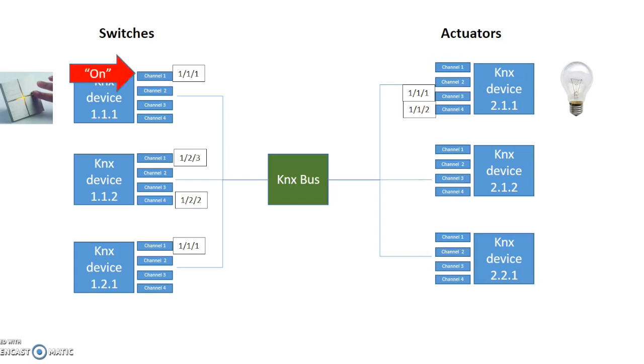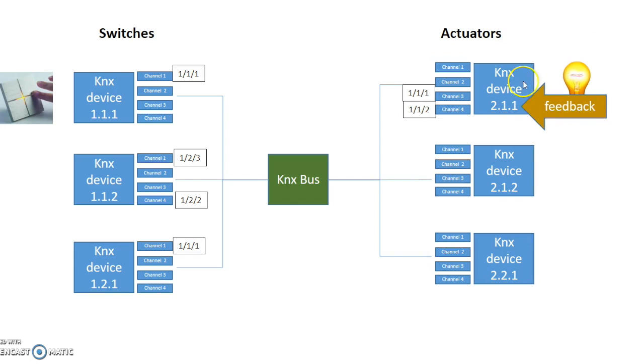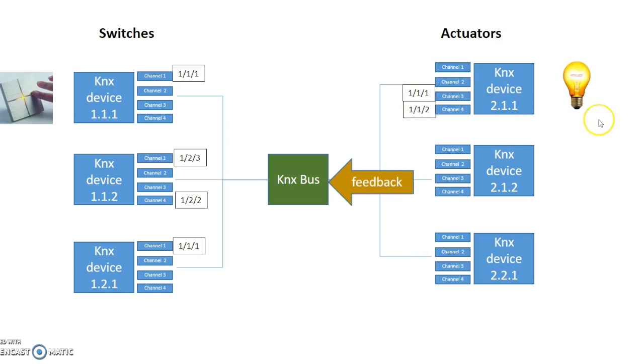If I were to press a button and switch this light switch on, it will send an on-message to the group address. That message flies through the bus, and anything associated with group address 1/1/1 will receive this on-value. In this case it comes through channel 3, and that turns on the light through the actuator. The device then sends feedback back to the bus — in this case through channel 4 — communicating that the light has been switched on.